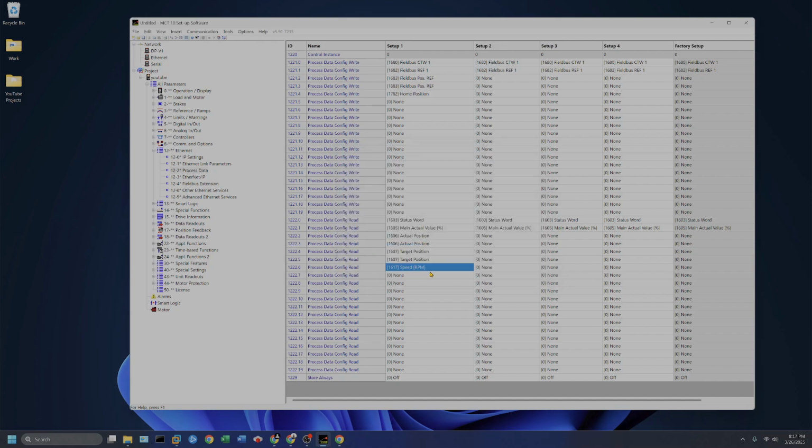Now, the speed can be plus or minus, so you could do this if you're not using a reversing bit, and that just gets into a lot of other crazy stuff which we can get into if you want to leave a comment. But you can just read back the RPMs, and then in the PLC do an absolute value if you wanted to see if your VFD is going forward or reverse or anything like that. So you would just select that, and then I'll make another video on how to set that up in the Ethernet IP section from the previous video where we had added that in there.